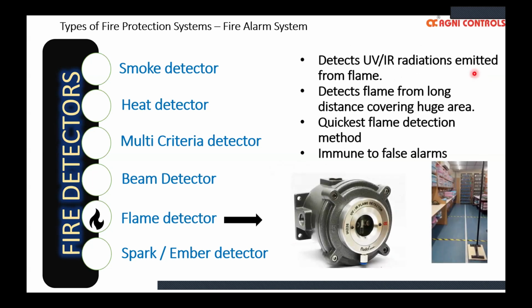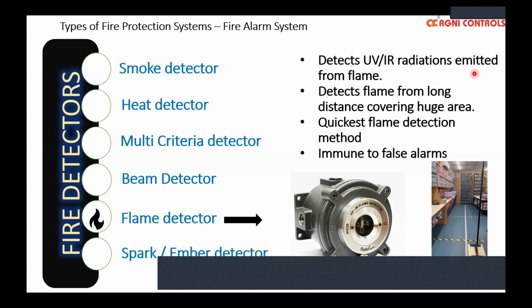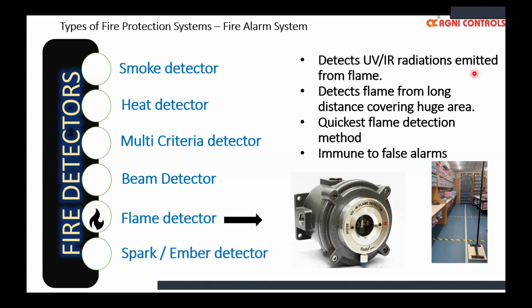So now we're going to talk about the flame detector. As I explained earlier, it captures the radiations coming off from the flaming fire. There are different radiations coming off from the flame, which are UV and IR. These detectors are suitable for long range coverage, and it is one of the fastest methods of detecting a flaming fire. And also, it is immune to false alarms.